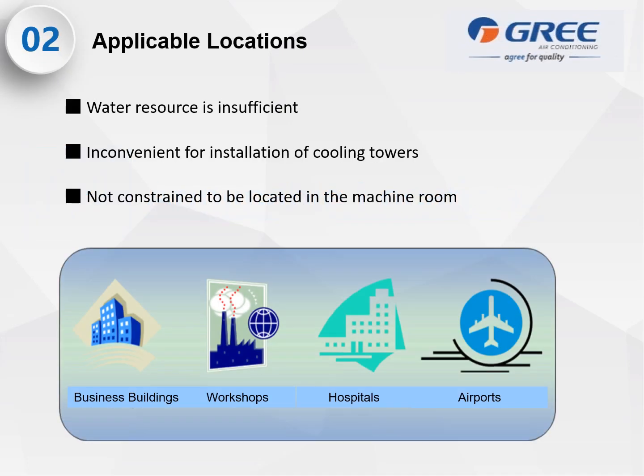For the applicable location, it can be used where water resource is insufficient or inconvenient for installation of cooling towers. If your roof deck is limited, you can use this, and it is not constrained to be located in a machine room, meaning you need not build a bigger machine room, as you would if you were doing a water-cooled chiller.